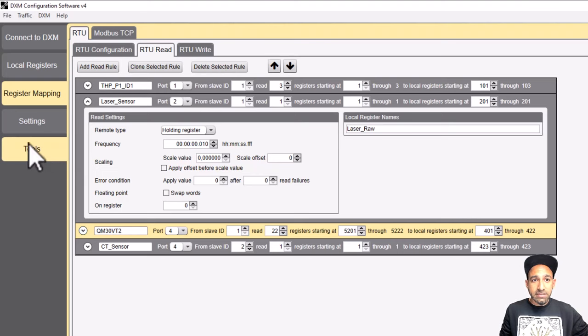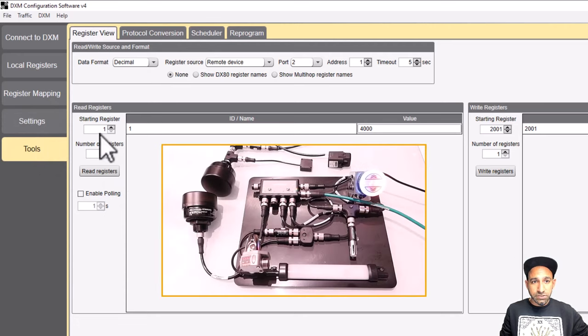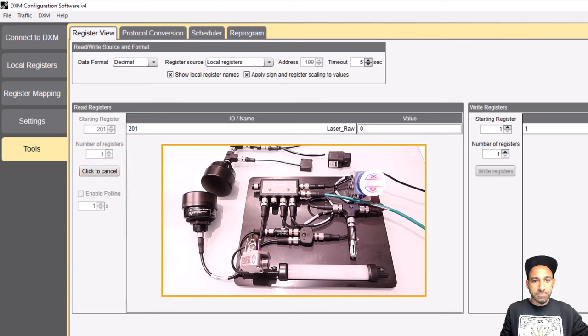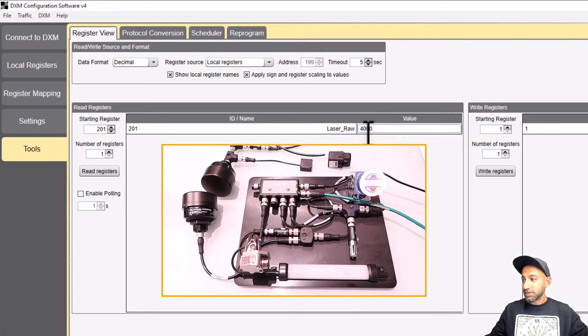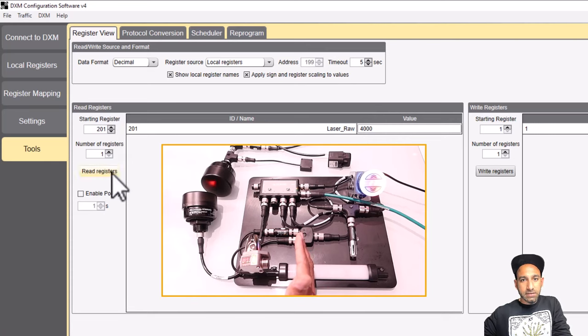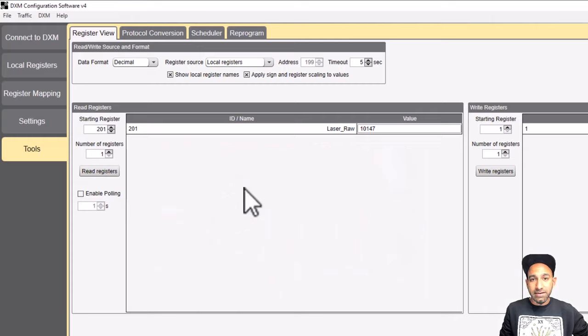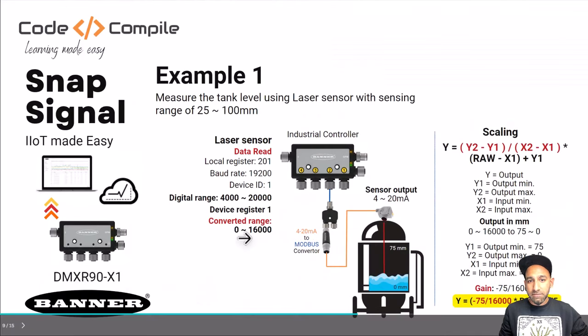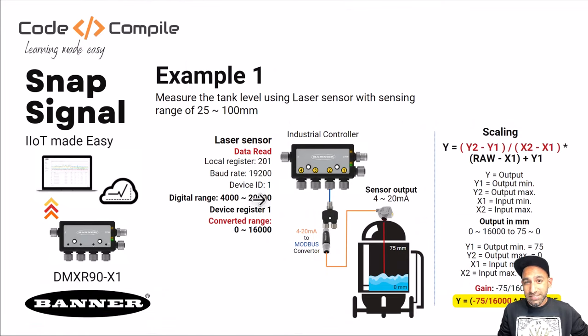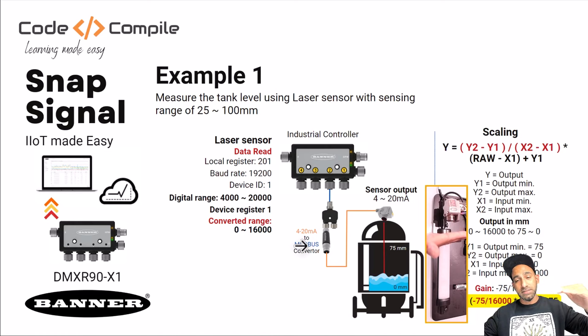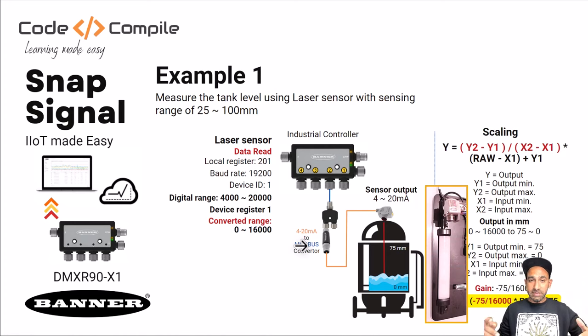Now I can read the value in my Modbus register. If I go to local register and type 201, I should get my raw value. I can see 4000 is coming. If I put my hand there again and read, the value changes — so I've successfully saved the value from the sensor into my controller. But the thing is, I also need to scale it.